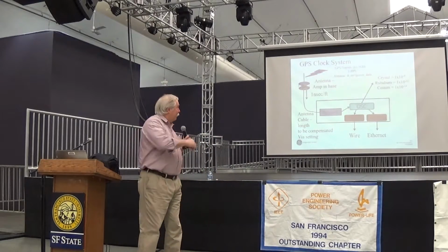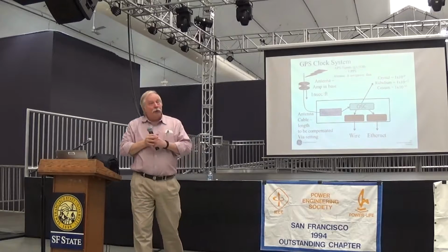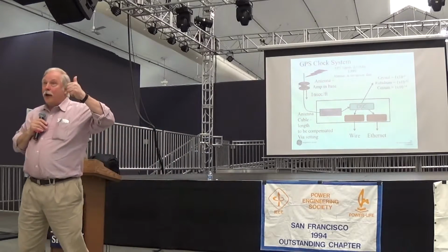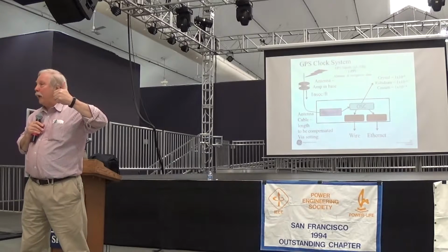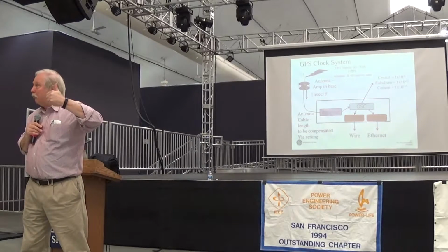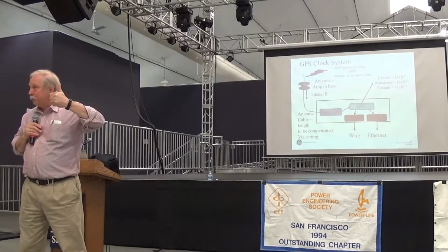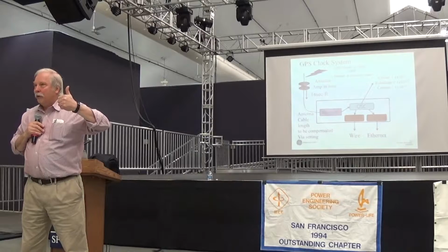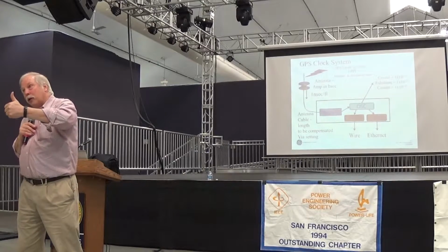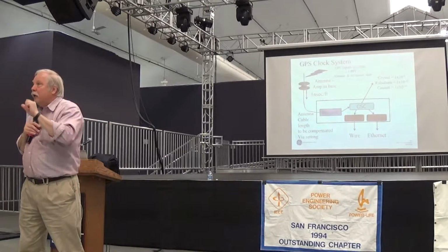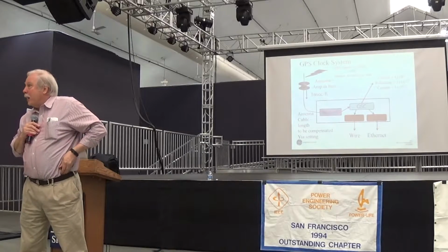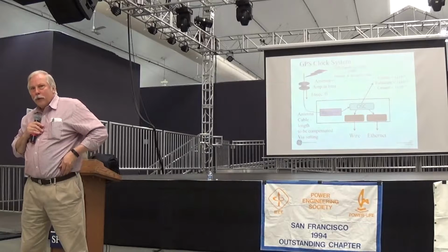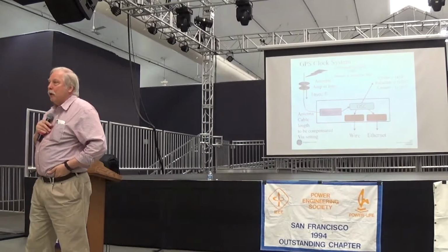So, now, these are the 2 primary functions of a GPS clock, but you will also find most GPS clocks also put out something called a 1 pulse per second time signal. But 1 pulse per second doesn't identify the pulse, so that has to be incorporated with a communication message that identifies the name of that pulse. The name obviously is the time when that pulse was emitted.